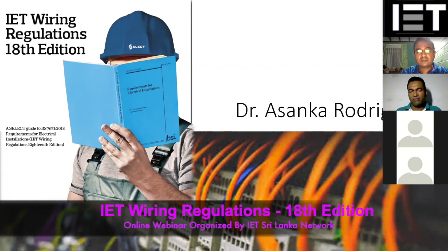TN, okay, we are silent on the earthing requirement, because it's equipotential bonding. So if you follow that equipotential concept, that fulfills your requirements. But for lightning, of course, the standard recommends having less than 10 ohms.